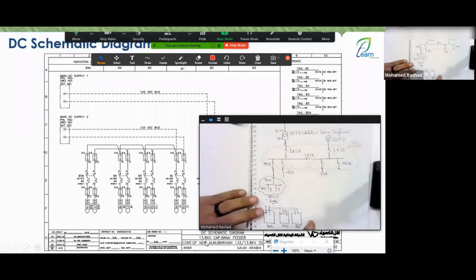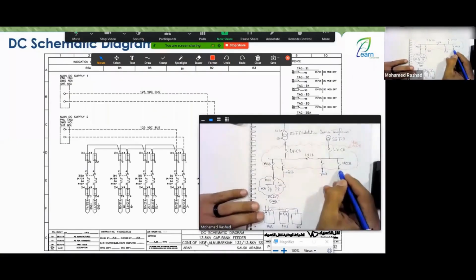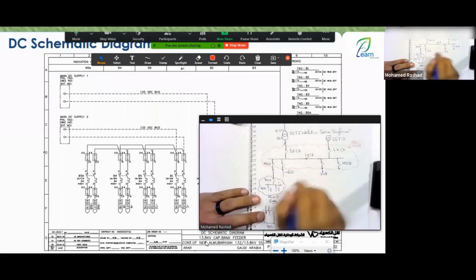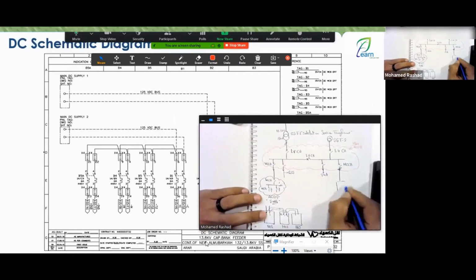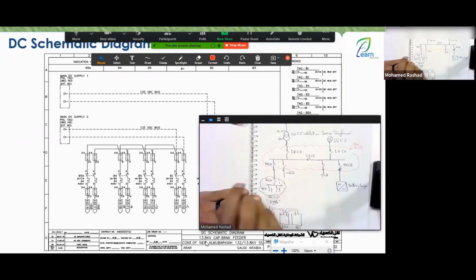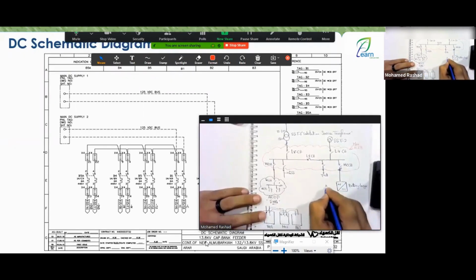Regarding DC circuits, what happens is, look, engineer, it takes a branch from these AC branches, which are the 3 phases, and then it goes into something called the battery charger. So what does the battery charger do? The battery charger takes an AC supply and converts it into a DC supply. So it converts from AC to DC, meaning you could call it an AC to DC converter.